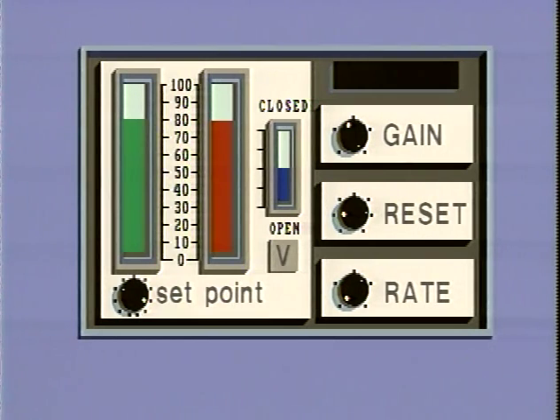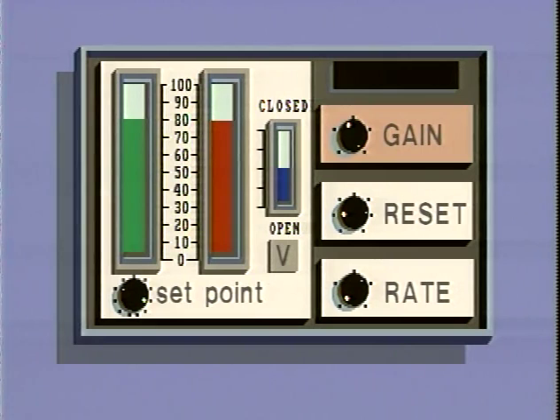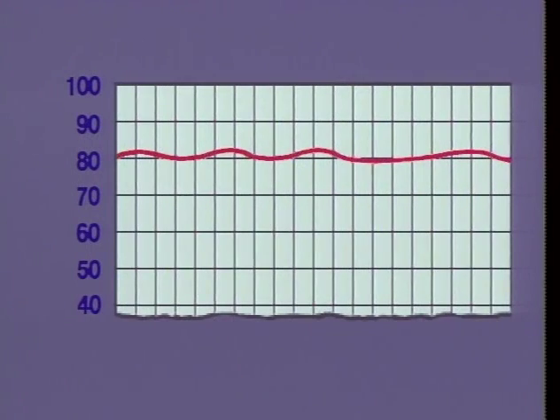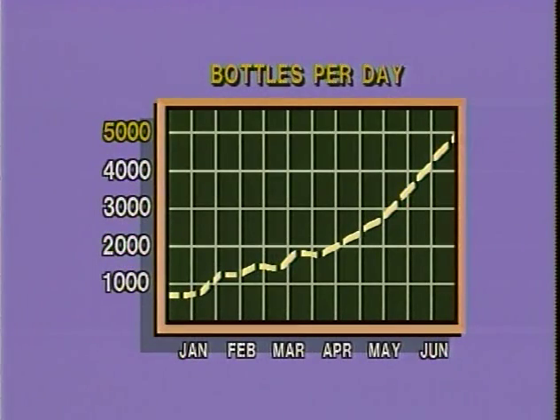The control instrument finally used in the plant was a 3-mode controller known as a PID controller. It contained proportional action, which responded to the size of the error to maintain the system under most conditions; integral action, which responded to the average error over a period of time to compensate for load changes; and derivative action, which responded to the rate of change in the error signal to speed up valve action when fast load changes occurred. With the PID controller, the temperature of the product in the heat exchanger was maintained within the required limits. The control system enabled the company to keep the high quality of its product, while it increased production by adding more production lines.